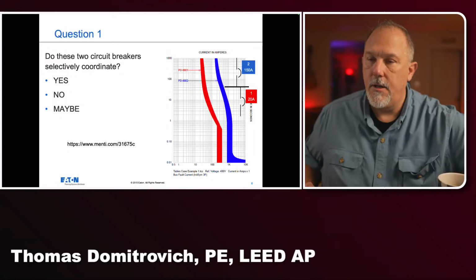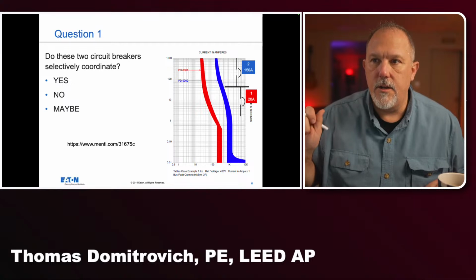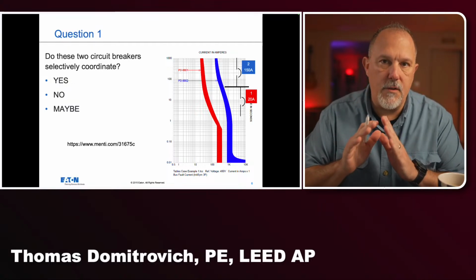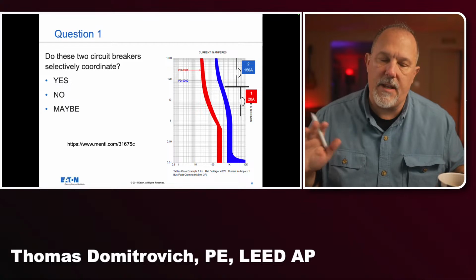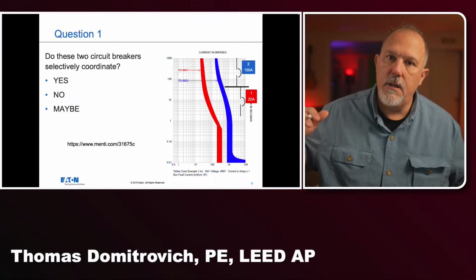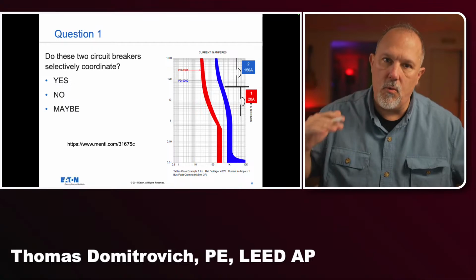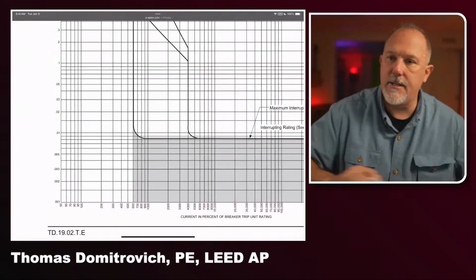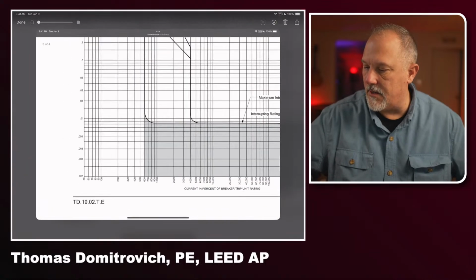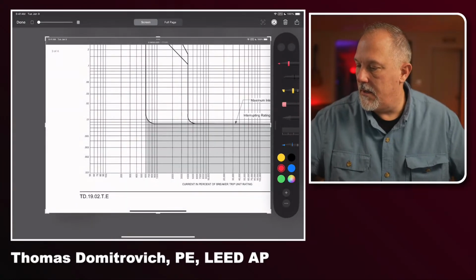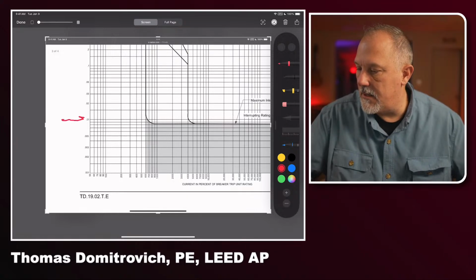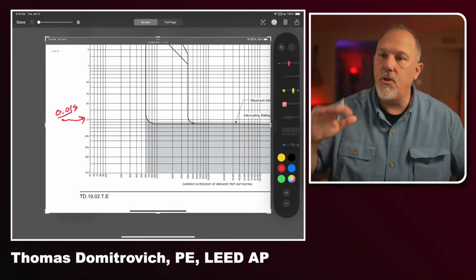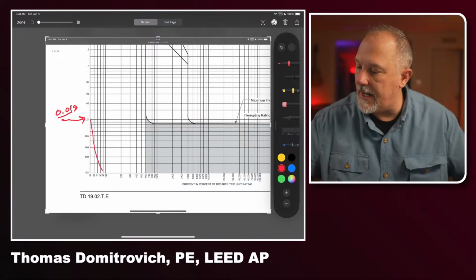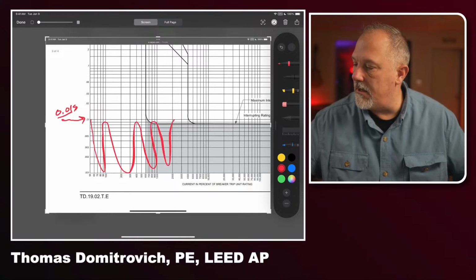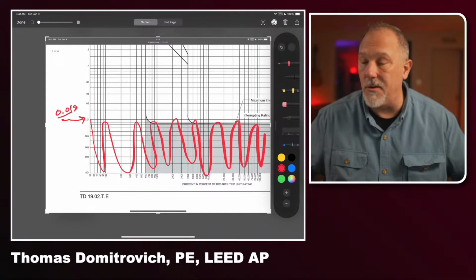Okay, so if we come down to this, now I'm going to go back over here. Notice the bottom of this screen. This TCC curve, and if you go to SKM and any of these manufacturers, they stop it down at 0.01 seconds. So if I come back to this, I'll point out that this is 0.01 seconds. So what you don't see on this other screen is anything down here. All of this is not being shown.